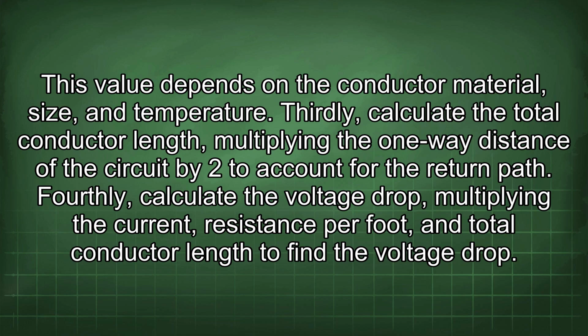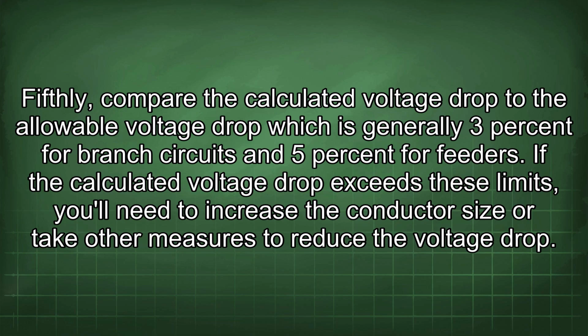Thirdly, calculate the total conductor length, multiplying the one-way distance of the circuit by 2 to account for the return path. Fourthly, calculate the voltage drop, multiplying the current, resistance per foot, and total conductor length to find the voltage drop. Fifthly, compare the calculated voltage drop to the allowable voltage drop, which is generally 3% for branch circuits and 5% for feeders. If the calculated voltage drop exceeds these limits, you'll need to increase the conductor size or take other measures to reduce the voltage drop.